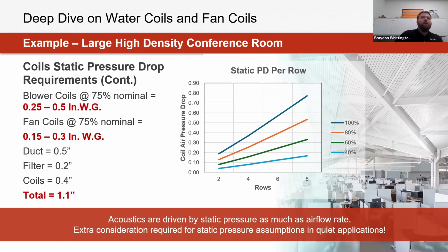So right off the bat, this really tells us that we're now within more of that performance window of maybe a more high performance fan coil or a blower coil, and eliminating the potential of more of a commodity style type, as we're starting to have a much higher amount of pressure that we're trying to compensate for within this system. Just to be clear, Braden, when you're showing the 0.4 on the coils, that's considered internal. You're looking at the total static for the system on just the thing. Exactly. Correct. Okay. Mm-hmm.